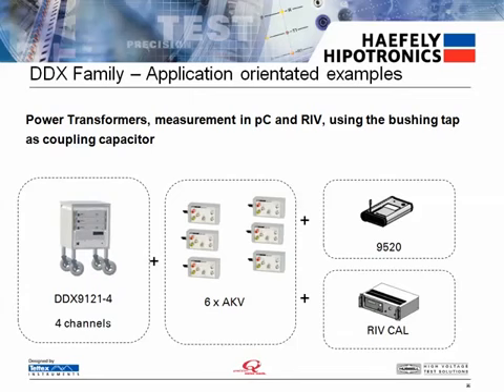For power transformer applications, we'll provide a multi-detector solution for simultaneous PD measurements of each phase. If a bushing tap is used as a coupling capacitor, then we only need to supply the measuring impedance. We suggest the 9520 calibrator as well as the RIV calibrator.